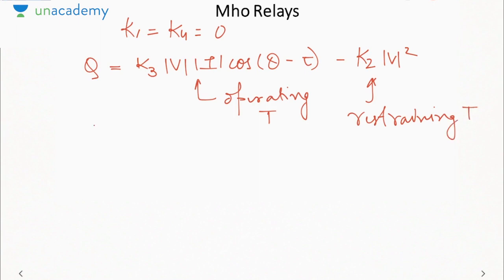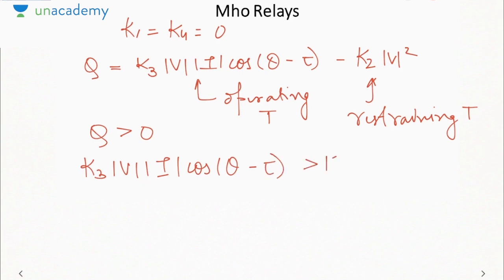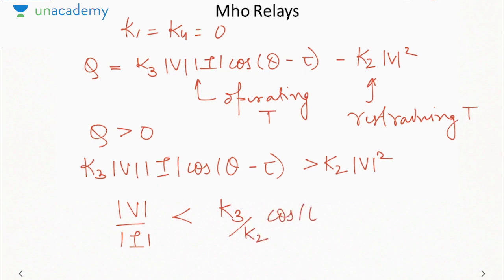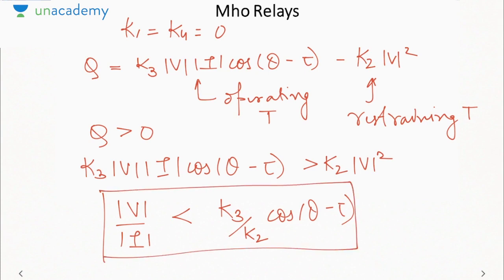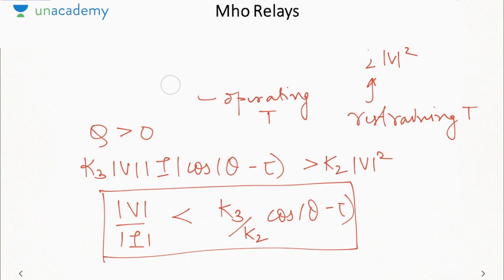Now this Q must be greater than 0 for relay operation. So K3 mod V mod I cos (theta minus tau) must be greater than K2 mod V square. So mod V by mod I must be less than K3 by K2 cos of (theta minus tau). Now based on this, I have to draw the characteristic of the Mho relay on the R-X plane. Let me show you how it is drawn.